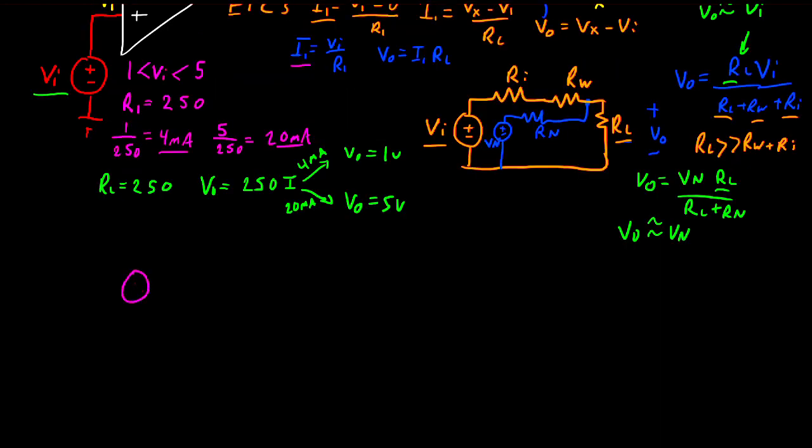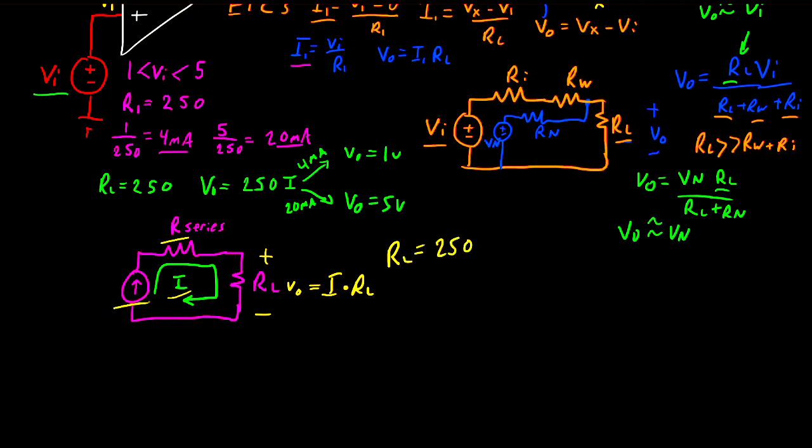Instead of using a voltage source, what if we had a current source, and we still have some series resistance, and this is RL, and this is our current going through. In this case, our series can be anything, and the current is going to remain the same because we have a current source. And the voltage we see at RL is going to only be based on I multiplied by RL. And now we're free to make RL be a smaller number, like 250. And because we're supplying this with a current source, our signal doesn't have voltage division, but the noise source that's still present in this system will have voltage division with this smaller number of 250. So this is greatly going to reduce the noise we see in our output, and it's going to prevent voltage division errors from our input.